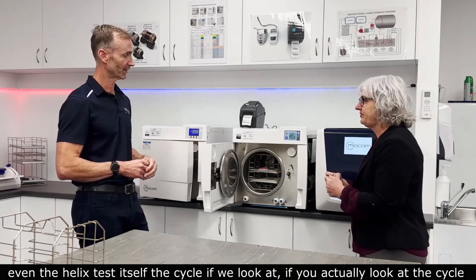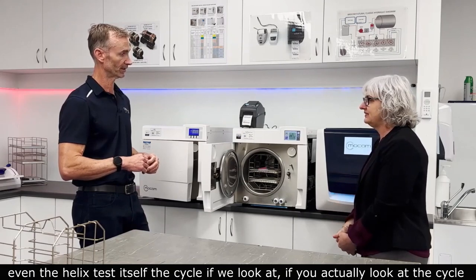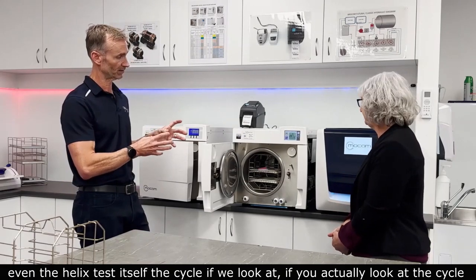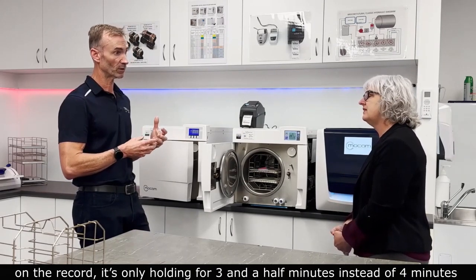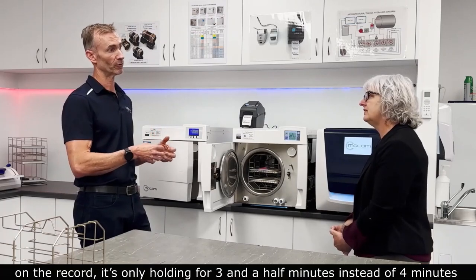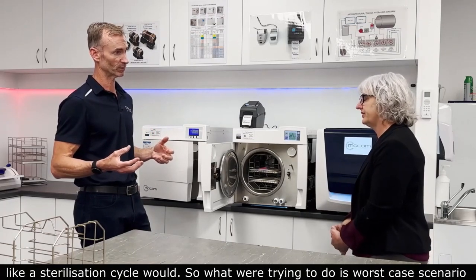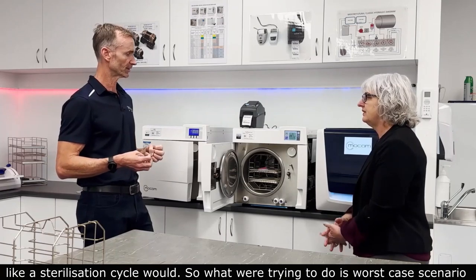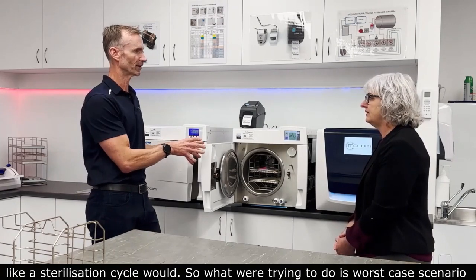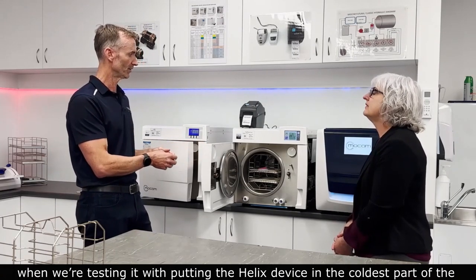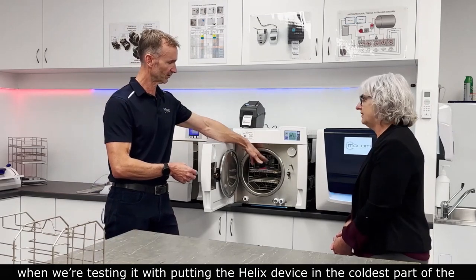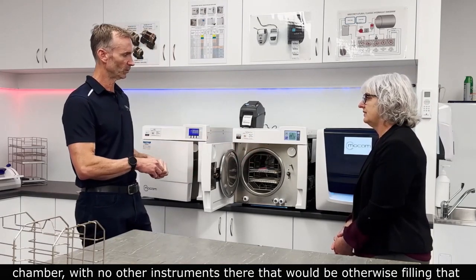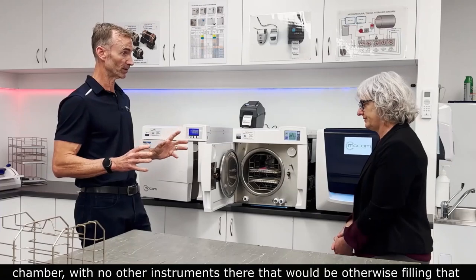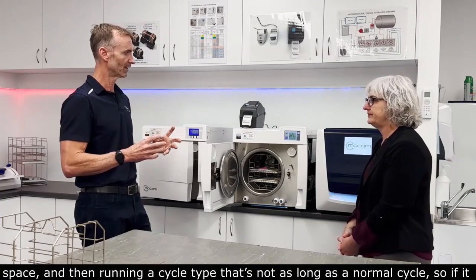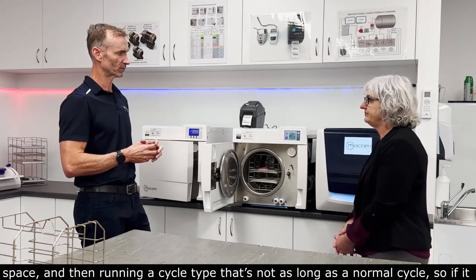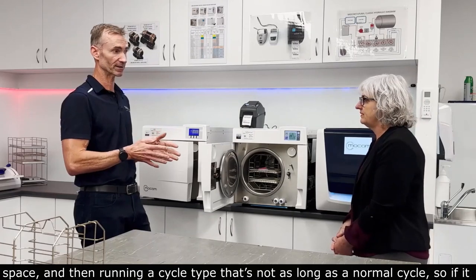And even the Helix test itself, the cycle, if you actually look at the cycle on the record, it's only holding for 3.5 minutes instead of 4 minutes like a sterilization cycle would. So what we're trying to do is give it the worst case scenario when testing it: put the Helix device in the coldest part of the chamber with no other instruments filling up that space, and run a cycle type that's not as long as a normal cycle.